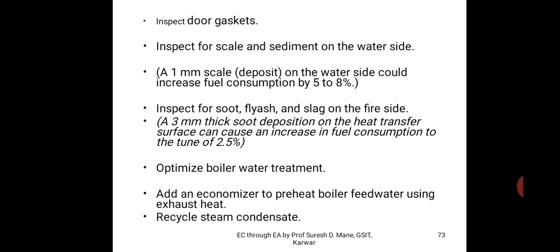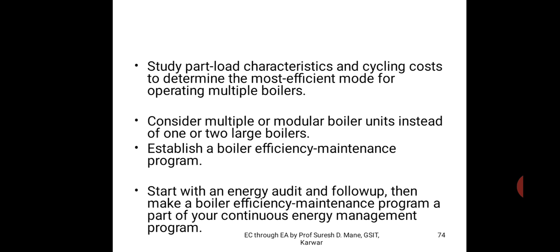We are also discussing part load characteristics. We should reduce part load operation; any equipment should always be run at full load. Even in your college, instead of one big generator for the entire college, people have now gone for small generators for each department. When there's a power cut, each generator takes care of the requirement of that department, because a big generator would not run at full load, it would run at part load, and part load efficiency is low.